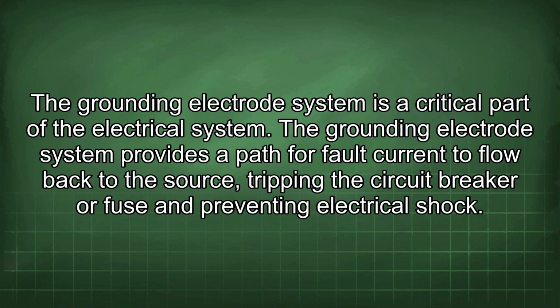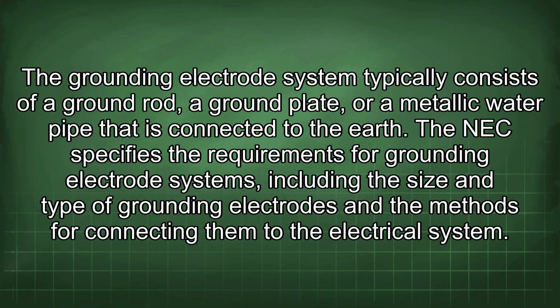The grounding electrode system is a critical part of the electrical system. The grounding electrode system provides a path for fault current to flow back to the source, tripping the circuit breaker or fuse and preventing electrical shock. The grounding electrode system typically consists of a ground rod, a ground plate, or a metallic water pipe that is connected to the earth. The NEC specifies the requirements for grounding electrode systems, including the size and type of grounding electrodes and the methods for connecting them to the electrical system.